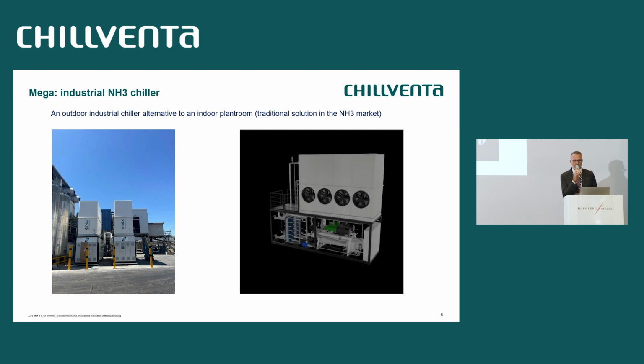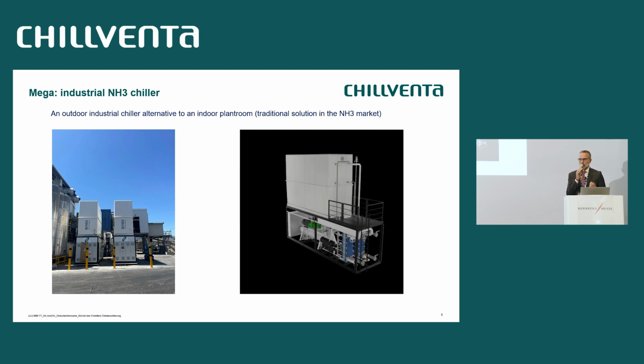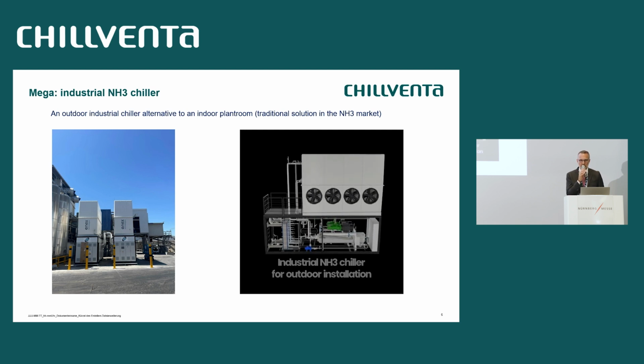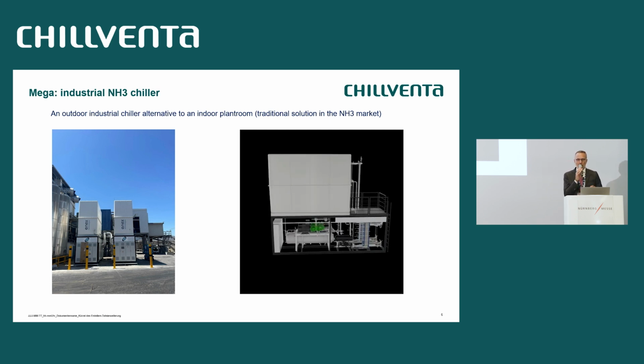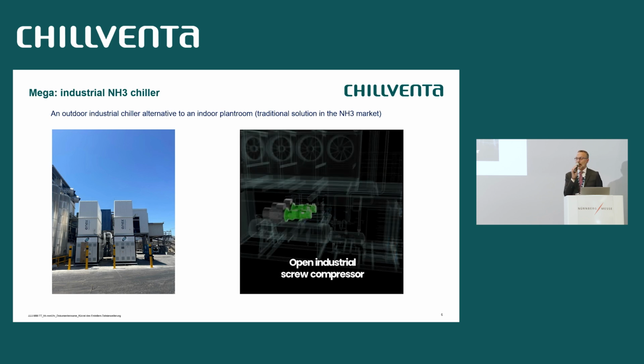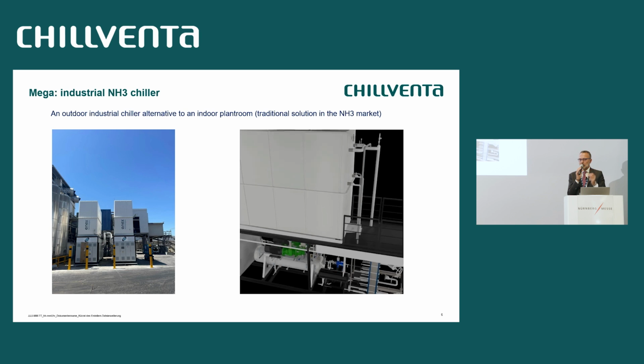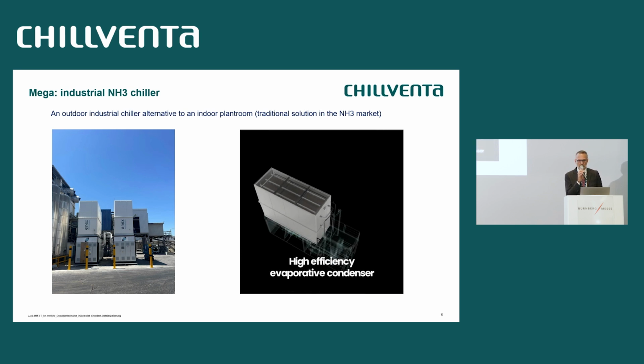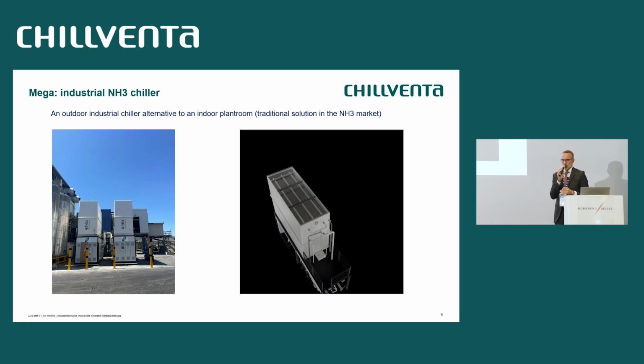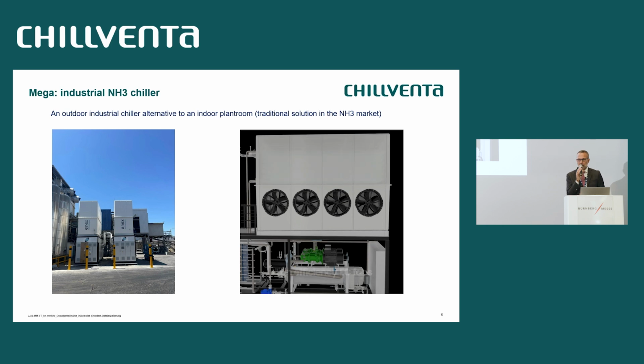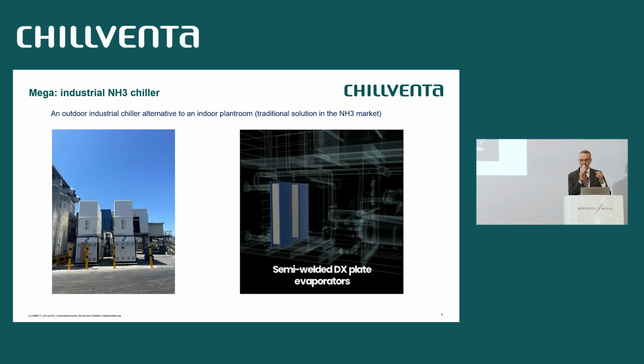This is an example of a concept we have developed. It's called a Mega. It's basically an outdoor industrial chiller, which is an alternative to an indoor plant room, the traditional solution in the ammonia market. You can see that it is a chiller featuring an industrial open screw compressor, and on top a very big evaporative condenser. The evaporative condenser is the most efficient way to condense ammonia because you have water in direct contact with the tubes where ammonia is condensing. So you can achieve a very low condensing temperature, even with an air-cooled chiller, and therefore the efficiency is comparable to the best ammonia systems that you can build in a plant room.